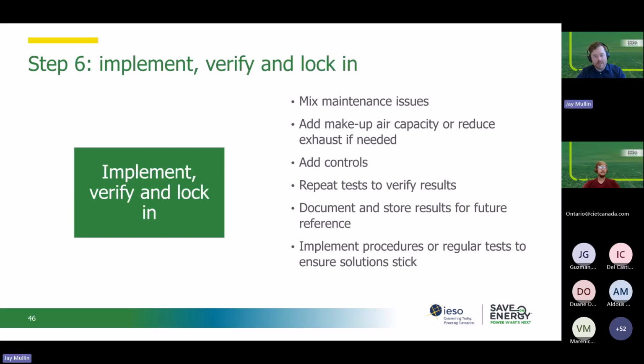And then, once all that work's done, you want to implement it and verify the results and lock in those changes. So, that should be fix maintenance issues, add any makeup air capacity or reduce exhaust as needed, add controls or refine your controls, then repeat your test to verify that the issue has been addressed, again, under different conditions. Make sure you document and store all of these results for future reference. And make sure, and this last one is really important, we haven't talked about it yet, is implement procedures or regular tests to ensure that these solutions stick.